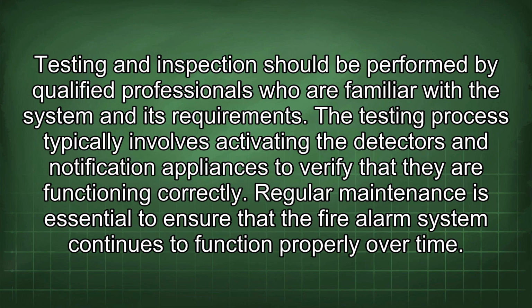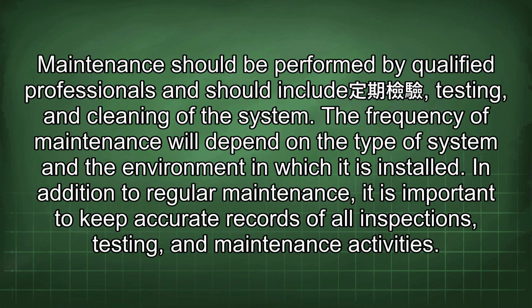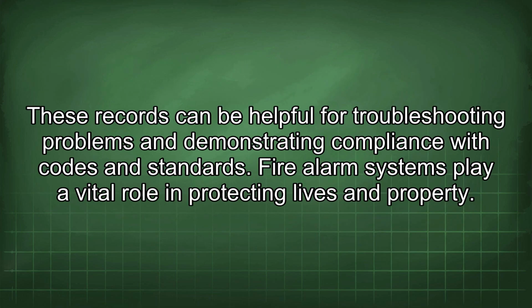Regular maintenance is essential to ensure that the fire alarm system continues to function properly over time. Maintenance should be performed by qualified professionals and should include testing and cleaning of the system. The frequency of maintenance will depend on the type of system and the environment in which it is installed. In addition to regular maintenance, it is important to keep accurate records of all inspections, testing, and maintenance activities. These records can be helpful for troubleshooting problems and demonstrating compliance with codes and standards.